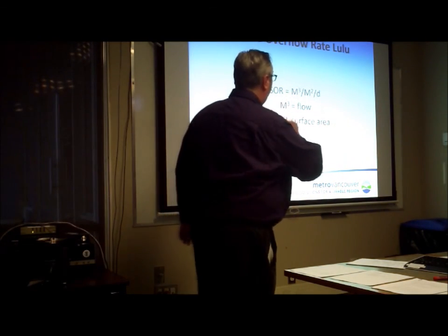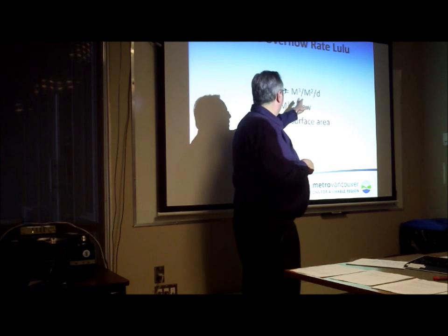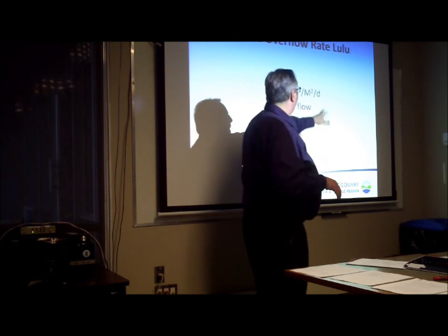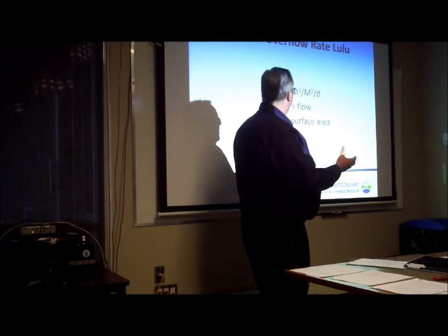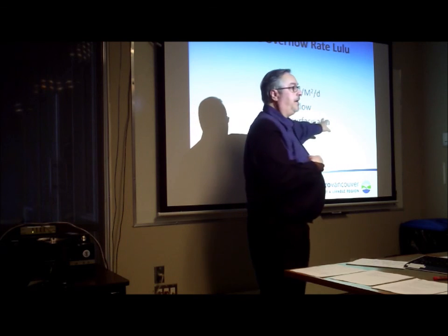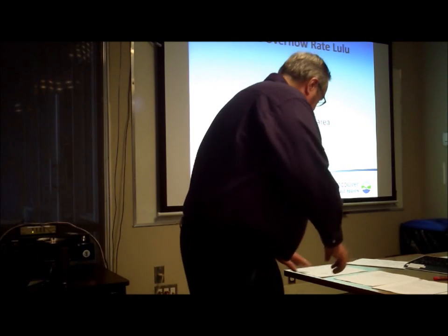So that brings us to our calculation. We're going to talk about surface overflow rate. The formula for surface overflow rate is meters cubed over meters square of surface area of a clarifier per day. So the flow gives you your volume, and the surface area of the clarifier gives you your meters squared.